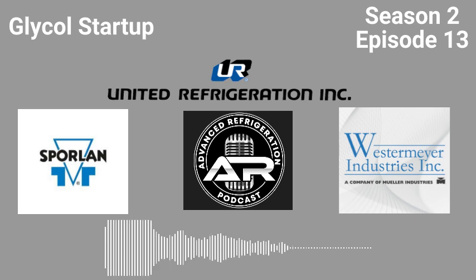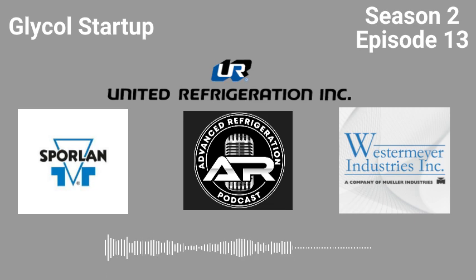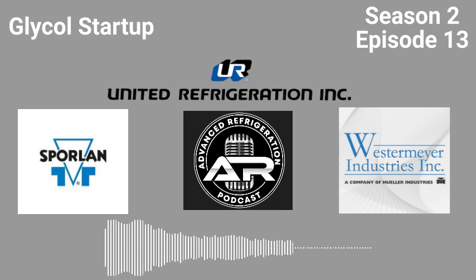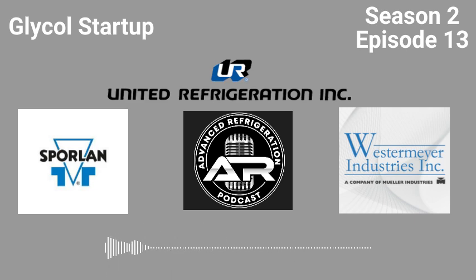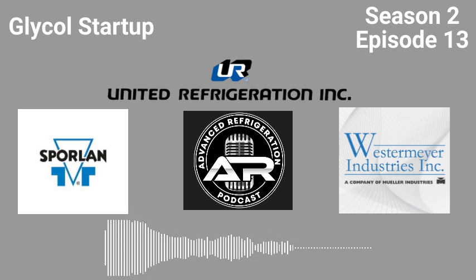And then you're going to drain that down. You're going to completely drain the system from all the low points. You're going to try to get as much out as you can. When I do this, I will hook an air compressor up to it and pressurize the supply and push everything out the returns. That way I can push as much water out as I can, because the goal here is to get all that water out.